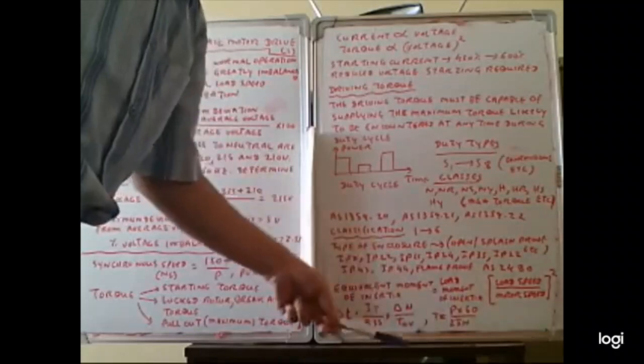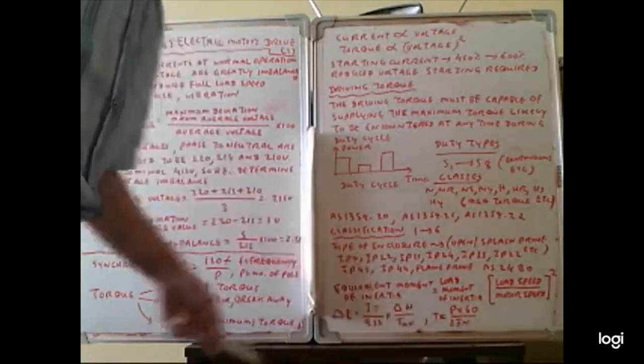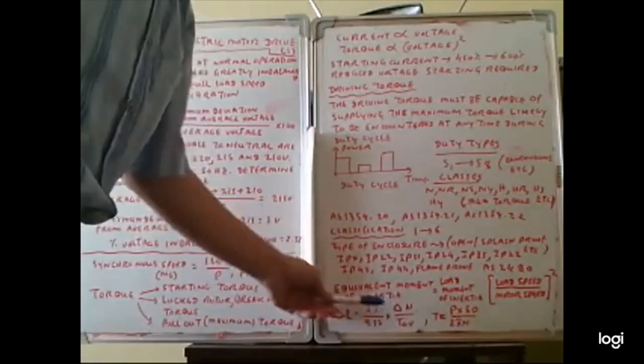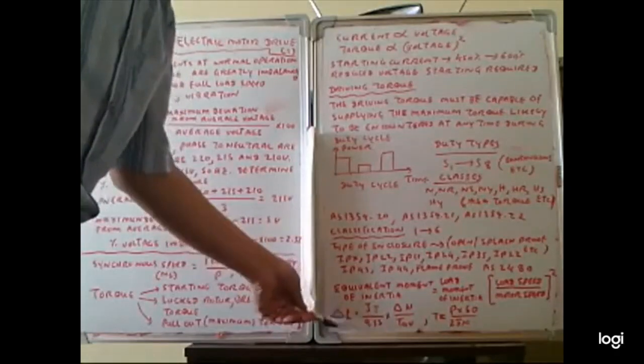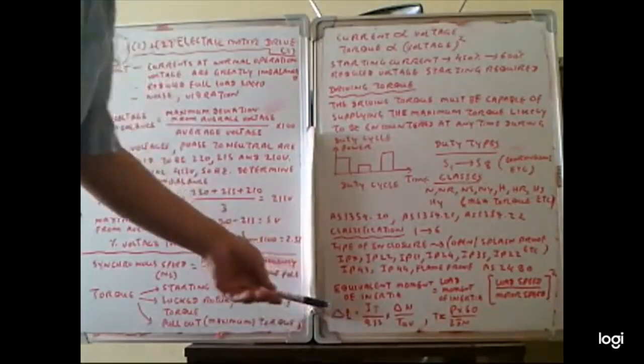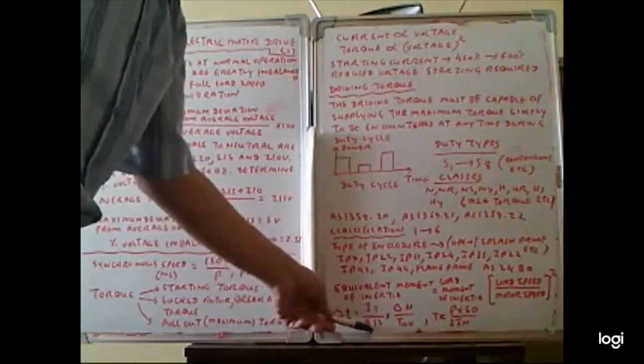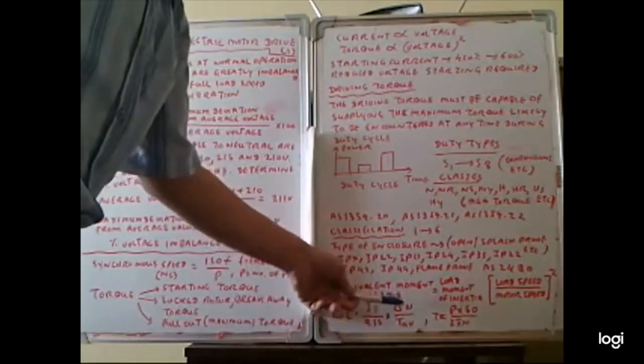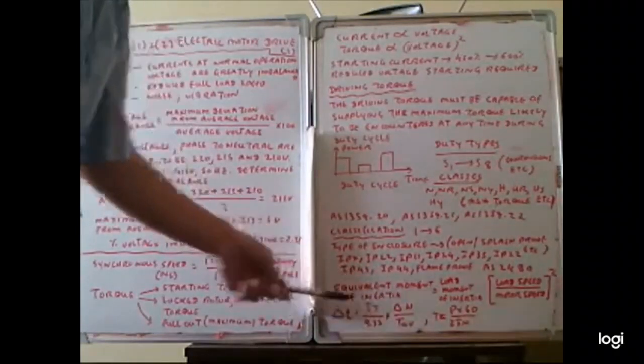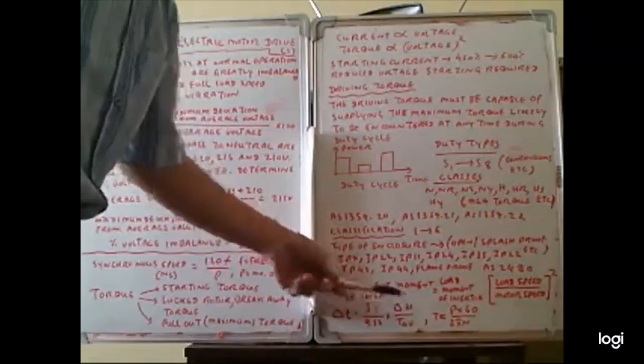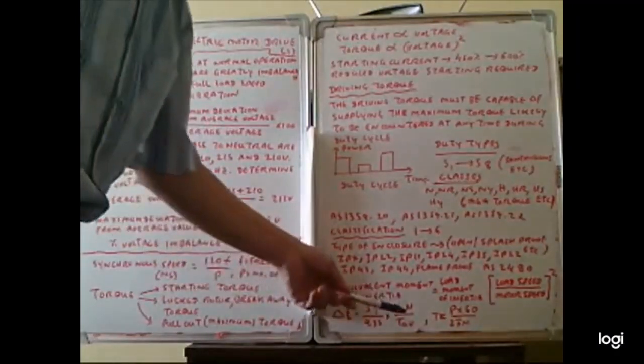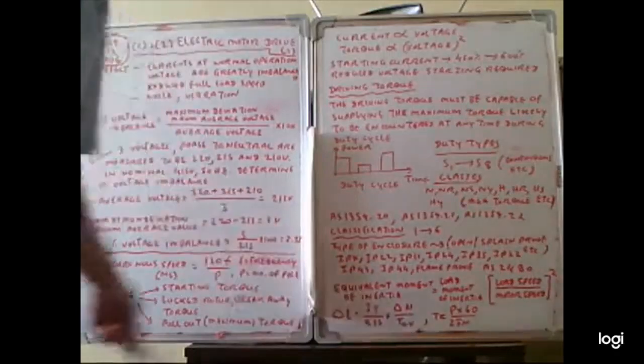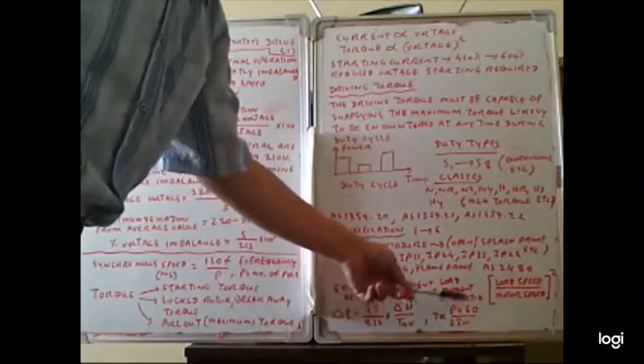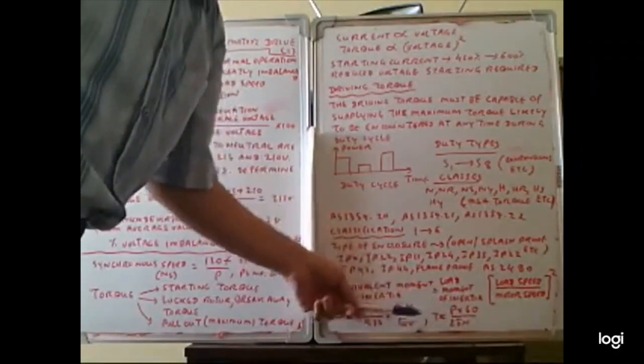P is the motor power in watts, N is the speed, T is the torque. So when the motor speed is changing, the time required to change can be calculated by this formula: delta t is equal to J_M divided by 9.55, multiplied by delta N divided by T_av. J_M is the motor inertia, delta N means the change of the motor speed, and T_av is the average torque. Torque is equal to P times 60 divided by 2 pi N, where P is the power in watts and N is the speed.